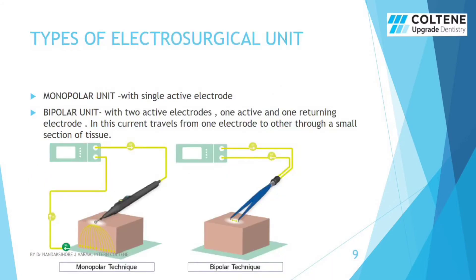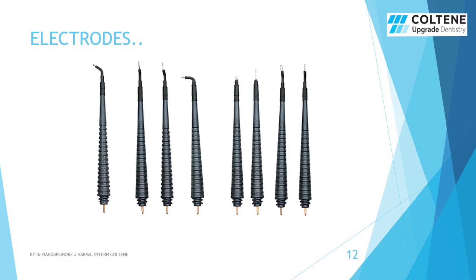What are the different types of electrosurgical units? They are monopolar and bipolar. Monopolar has a single active electrode. In the case of a bipolar unit, there are two active electrodes — one active and one returning electrode — and the current travels from one electrode to the other through a small section of tissue. Electrode types include coagulation ball type, loop type, straight fissure type, knife type, and others.